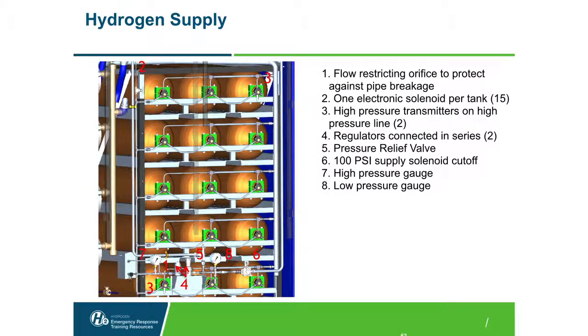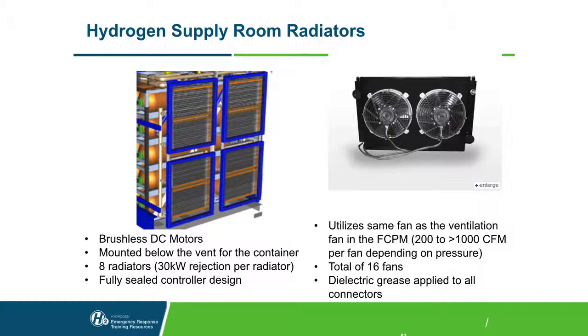Here are the flow restricting orifices to protect against pipe breakage. The solenoids are here, and various other safety systems for the overall hydrogen storage. As I mentioned, there is cooling that's required for the fuel cell, and that takes place with these radiator fans. And that's one thing I need to confirm with the manufacturer. I believe that these are class 1 or class 2 explosion proof, basically, or intrinsic, and I have to confirm that. Because they are on the hydrogen storage side, and that was basically an element of real estate where they could be placed. So they needed that much space for the fans.